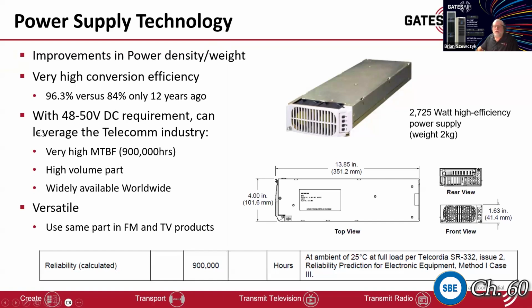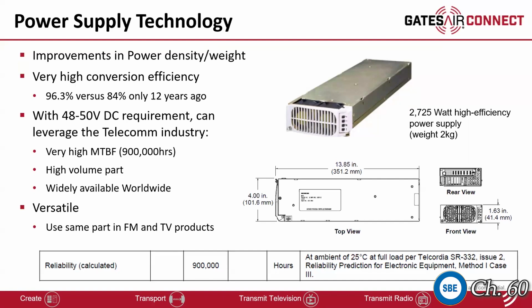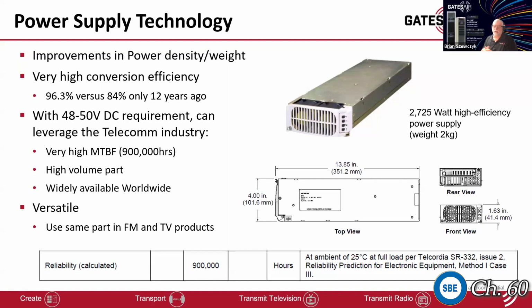Most of the RF devices today are in the 48 to 60 volt range. The power supplies that we chose to use have a very high mean time between failure of 900,000 hours typically. And when you look at the number of supplies that are deployed at this point in our products, both radio and TV, it's probably north of 50 or 60,000 power supplies, and very rarely do we hear of a failure.